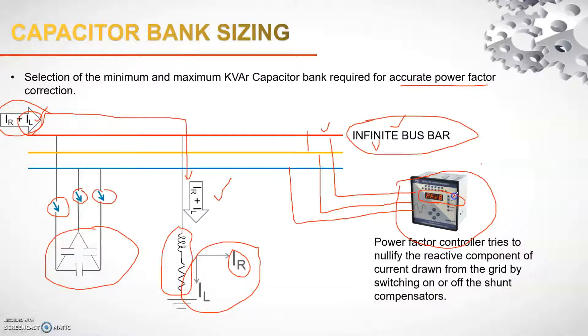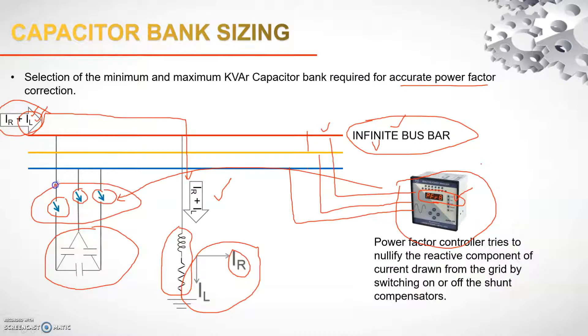If the set value in the power factor manager is unity and the power factor decreases to say 0.98 due to the reactive component, the manager will command the switches to close. These switches are contactors whose auxiliary coils are connected to one of the channels of the power factor manager. The power factor manager commands these switches to close depending on the value of current.